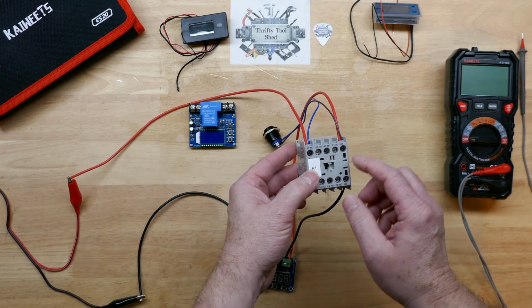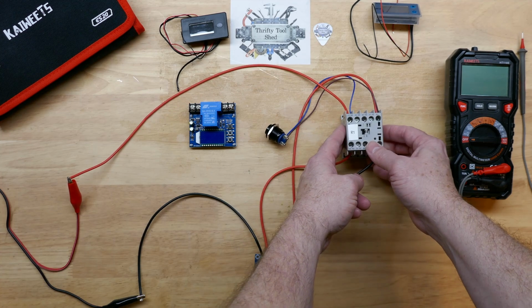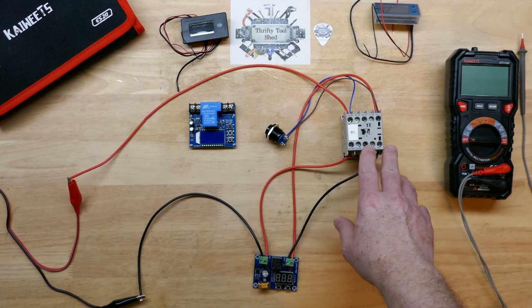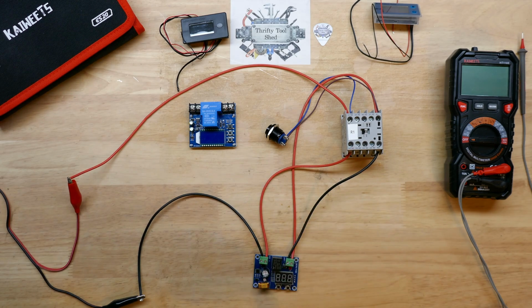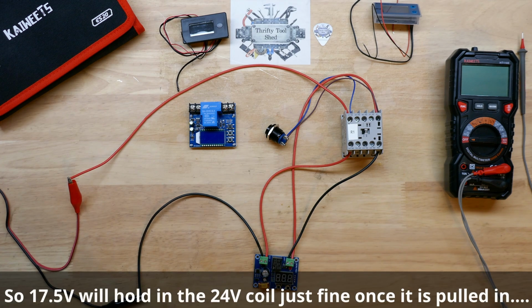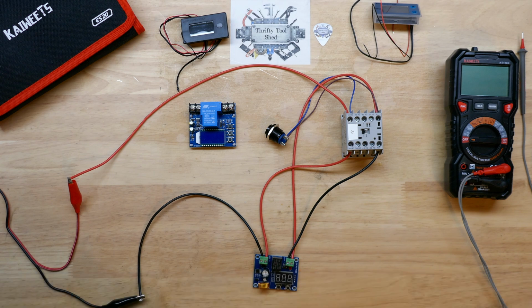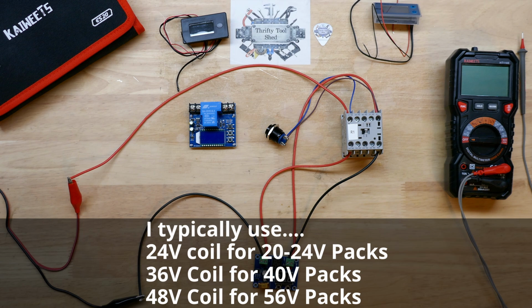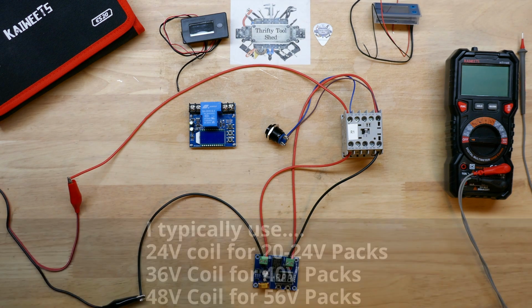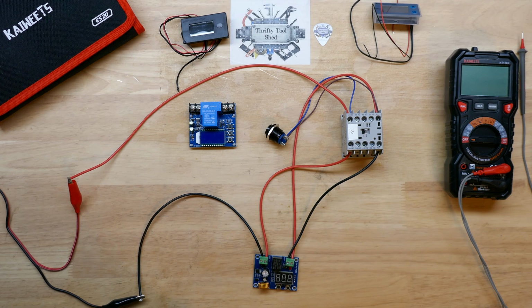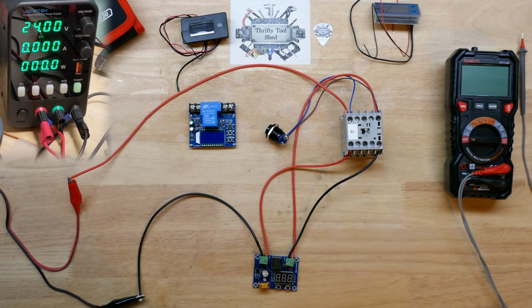So there are many options, but one thing you'll need to drop out completely from a battery is going to be a latching relay. And this example circuit here is exactly that. So this is a 24 volt coil, and that's very important that you have the right coil for your battery voltage. Most coils will hold in fine at a little bit reduced rate once it pulls in, but sometimes it is hard to find a coil rating for a voltage that your battery may be using. But to show how this works here, I'm going to cut my power supply on. I have it set for about 24 volts.